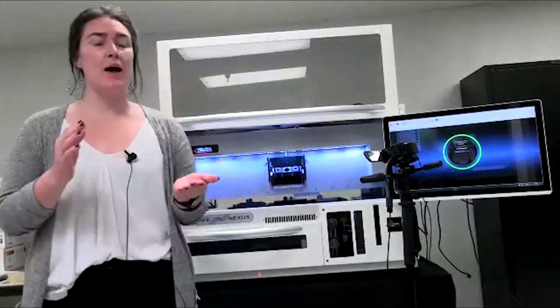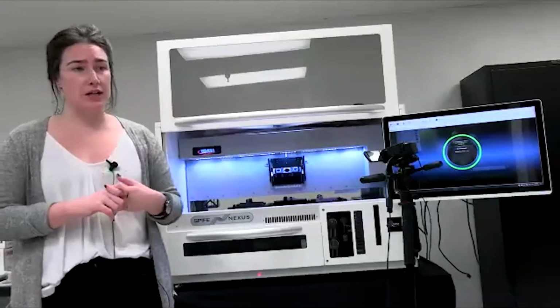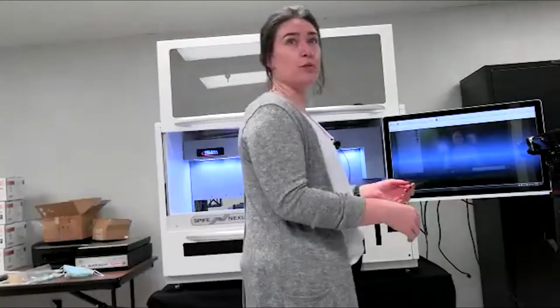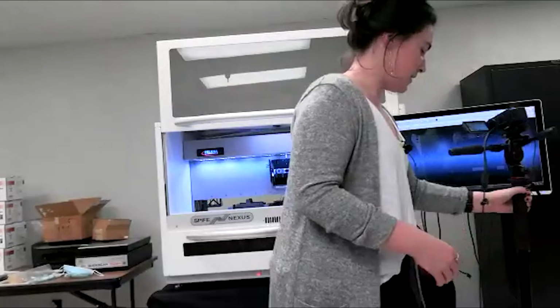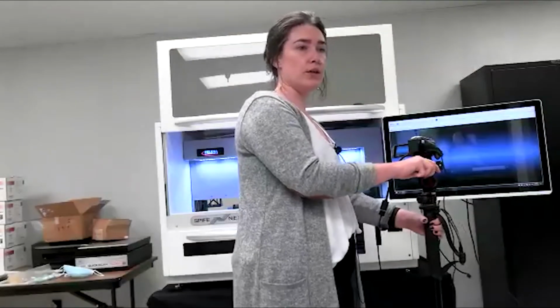Okay, so for once a week maintenance, I would recommend that you wipe down your electrodes on that platen cover, and that you also flush the fluid lines of the machine with a 10% solution to prevent any growth in the tubing. And we have options for both of those maintenance procedures in our maintenance menu. Would you like to switch to 2? Thank you. Or to 1. There we go.